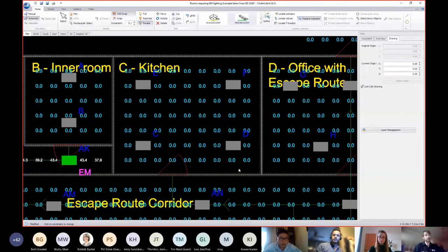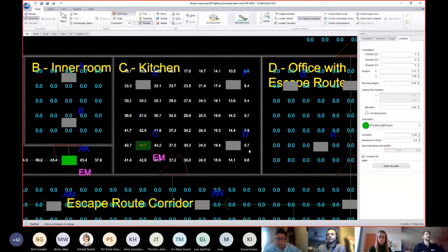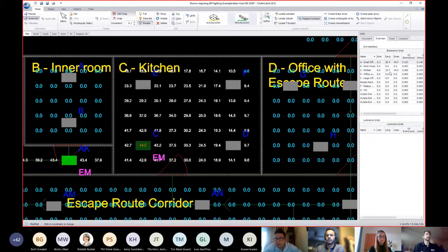We need an increased level here in order to get an average of 15 lux, and of course the emergency fitting has to be placed near to the door. Now we can see in this room our average in C, the kitchen, is now 24.7 lux. So we've lit that adequately.